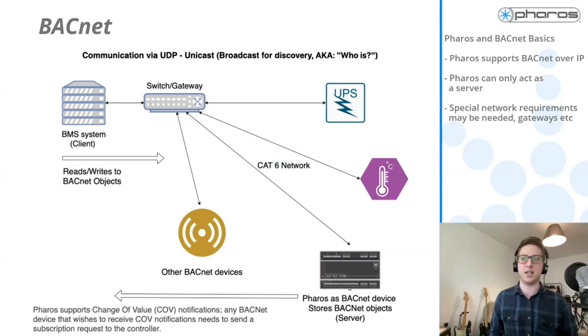There is one other thing though that I need to quickly say, which is that we support something called COV, change of value notifications. Effectively, that's where Bacnet wishes to receive COV notifications every single time a value is changed on a server device. I'll go through this in a little while, but it's a really good method to push data back to the BMS system rather than having the BMS system poll us for data.